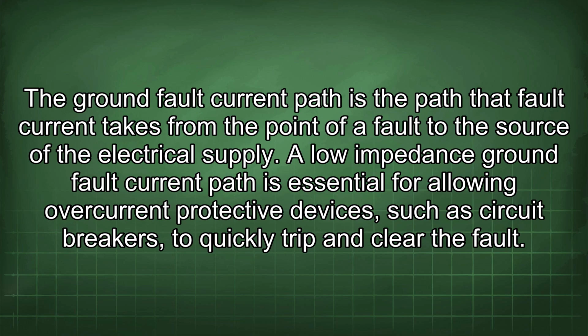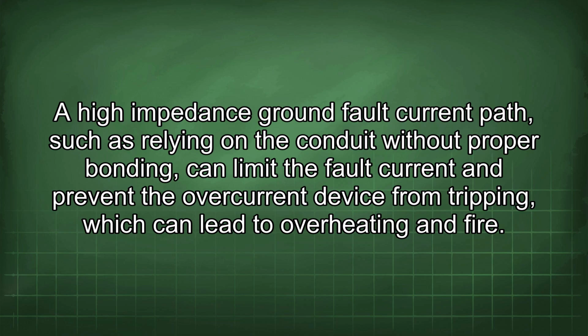The ground fault current path is the path that fault current takes from the point of a fault to the source of the electrical supply. A low impedance ground fault current path is essential for allowing overcurrent protective devices, such as circuit breakers, to quickly trip and clear the fault. A high impedance ground fault current path, such as relying on a conduit without proper bonding, can limit the fault current and prevent the overcurrent device from tripping, which can lead to overheating and fire.